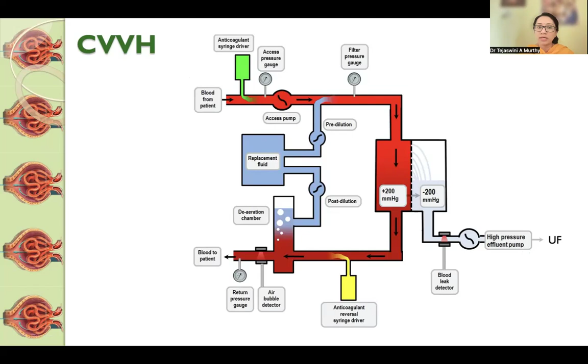So blood from the patient, blood flows around 200 to 300 ml will go because these are pressure dependent. So blood flows are a little higher when compared to CVVHDF. Then an anticoagulant will be injected. Then it goes through a pump and reaches the filter. And then in the filter, through convection, the solute along with the fluid will get filtered across the semi-permeable membrane. And then we will use a replacement fluid in the bubble trap or deaeration chamber and return back the filtered blood to the patient.